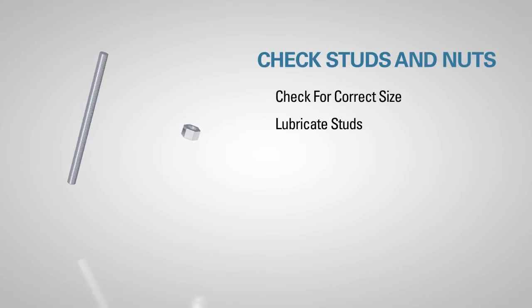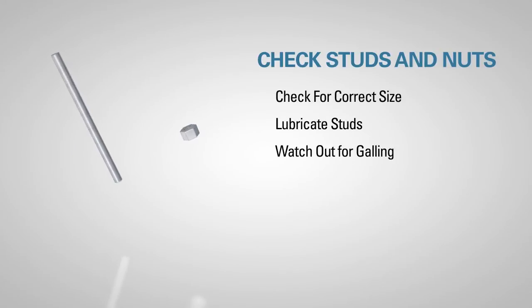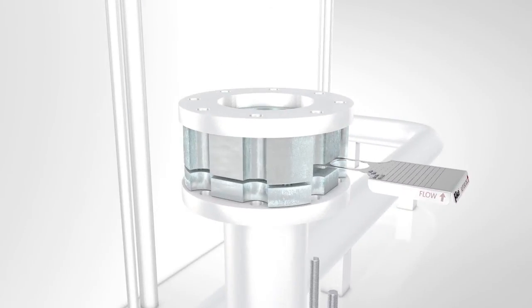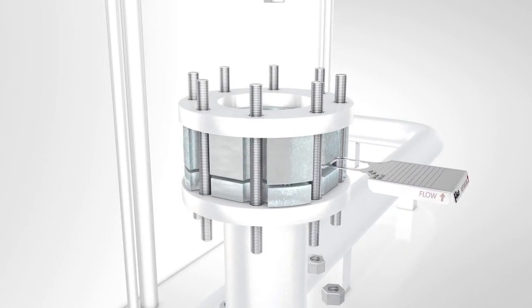Check to see that all studs and nuts are the correct size. Lubricate the studs with a light, free running oil such as 20 grade. Studs and nuts that show evidence of galling should not be used. Insert the studs into the flange and finger tighten.